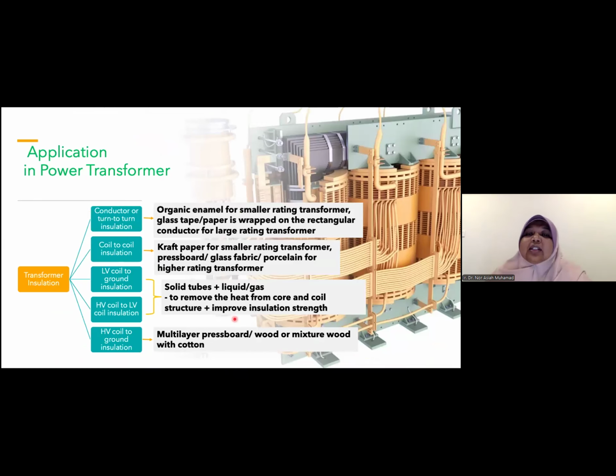So now we look at the detail of the transformer insulation. We have the conductor or turn-to-turn insulator. Here we have the turn-to-turn insulator. Most of it is organic enamel for smaller rating transformers. We also have glass tape or paper wrap on the rectangular conductor, which is for large rating transformers. Then we have the coil-to-coil insulator. We have kraft paper for small rating, press board for higher rating, or porcelain for higher rating.